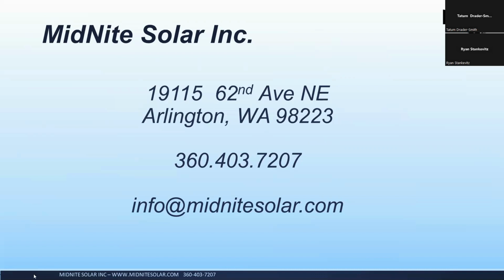I think historically the component manufacturers like MidNite or the other ones in the industry that don't do a complete standalone product tend not to worry a lot about the other components in the system that aren't theirs. I don't know what others are doing for that, but that is a real issue, because if you take a SimpliPhi battery, for example, a 48-volt battery, and you instantly feed it 500 volts, the BMS in there isn't designed to deal with that. And when you start opening FETs under extreme high voltage, a FET will usually fail in a shorted condition. Let's say it's not even a hardware failure. Let's say somebody in the room takes a Rosie, and they've got 2 strings of PV, and they don't quite pay attention, and maybe they get the strings in series instead of parallel, and they feed down 1200 volts instead of 600 volts. That Rosie is going to fail dramatically, and when it does, it's going to pass that through.